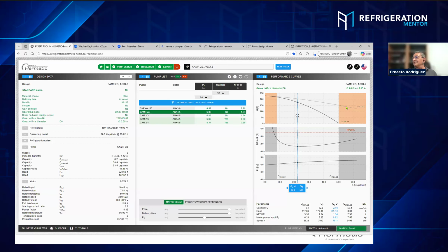The motor is 3 HP, for example. If you are pumping too much fluid, it's going to exceed the mass flow capacity of the pump. And that orange is how much liquid is going to return to the vessel. For example, in this sample, it's going to return approximately 8 gallons per minute to the vessel, and the maximum flow of the pump is 50 gallons per minute with no problem.